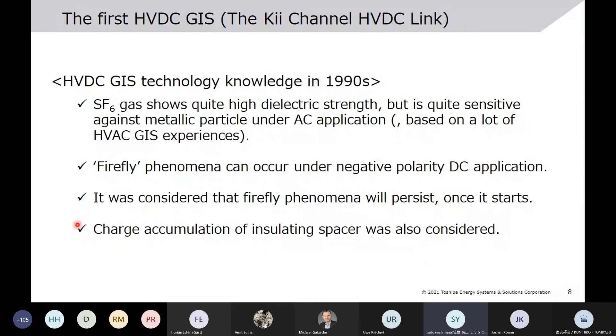And in consideration of such knowledge, we defined the main points of HVDC development. At first, we defined that the maximum length of metallic particle is 3 millimeters, and no breakdown by LIWV, even under firefly condition. And also no breakdown by LIWV, even if the metallic particle is attached on the weakest point of the insulating spacer. In order to realize such required condition, particle traps are arranged on the high voltage conductor and the grounded metal enclosure in order to make metallic particle harmless. And also coating is arranged on the inner surface of the grounded metal enclosure.